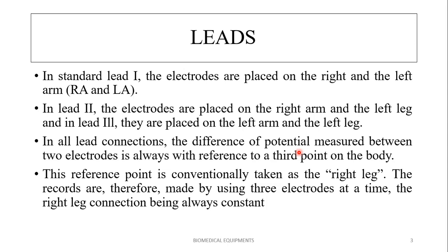What are the types of leads? In standard Lead 1, the electrodes are placed on the right arm (RA) and left arm (LA). In Lead 2, the electrodes are placed on the right arm and the left leg. In Lead 3, they are placed on the left arm and left leg. In all lead connections, the potential difference is measured with reference to a third point — conventionally, the right leg is used as the reference point.